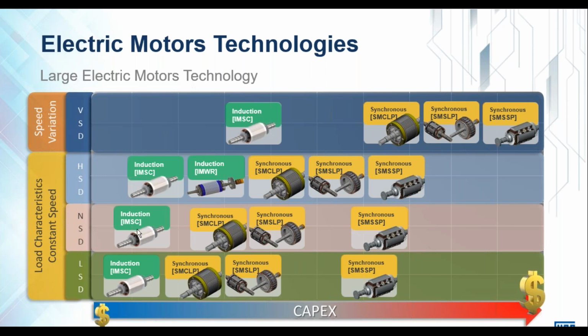In the normal starting duty, the same principle applies. High starting duty, the same principle applies. Induction motor would obviously be on the lower end of the spectrum. For high starting duty, an induction motor is not always the right option because it does have a limitation in terms of its starting torque. A wound rotor induction motor can solve this problem by adding resistance into the rotor to increase its starting torque. And then for speed variation applications with VSD, of course, the induction motor with VSD is the least expensive.